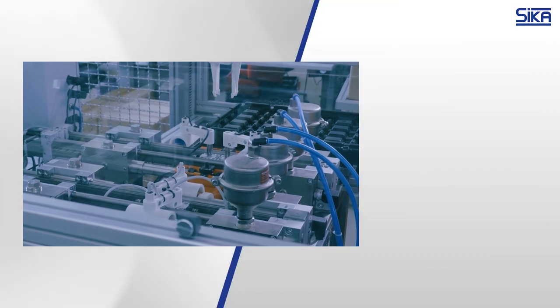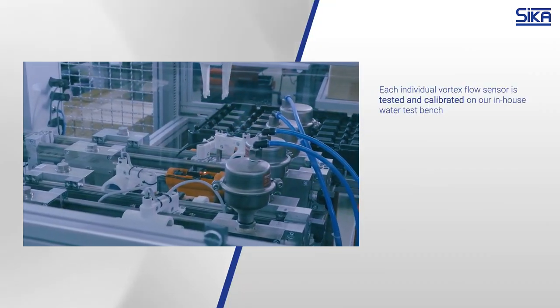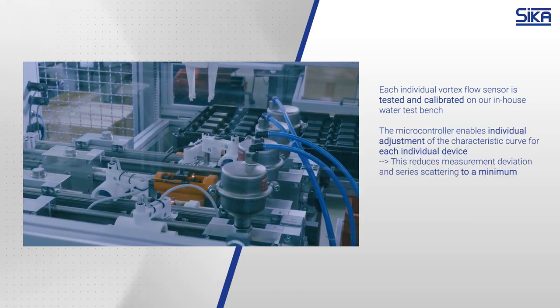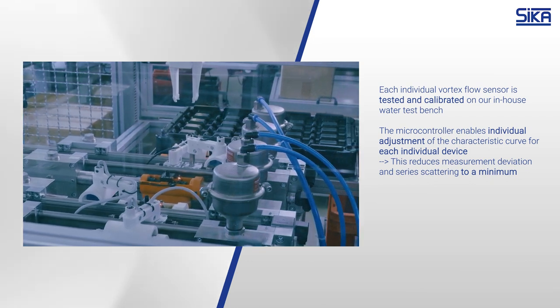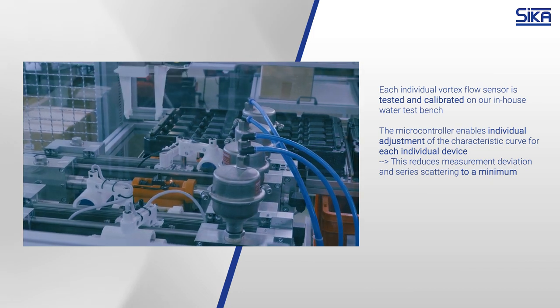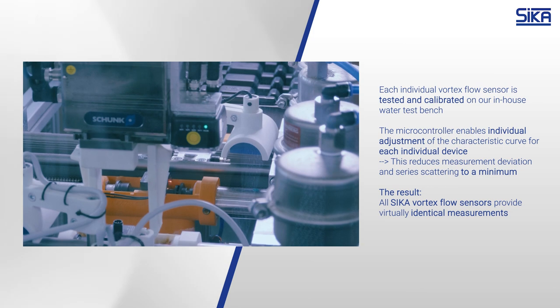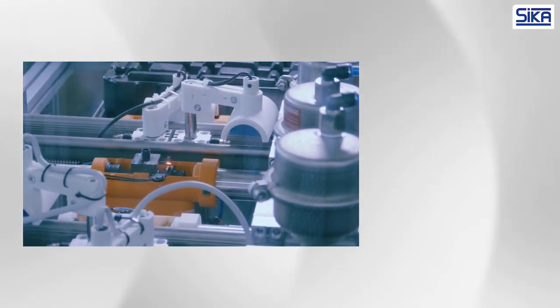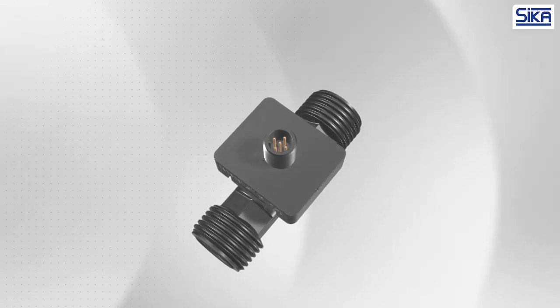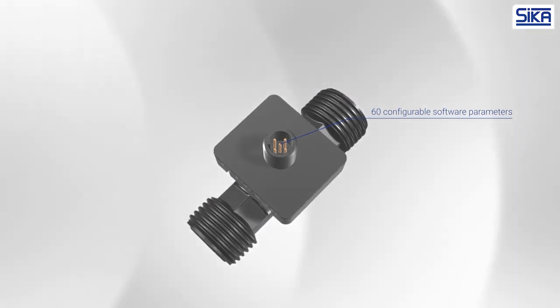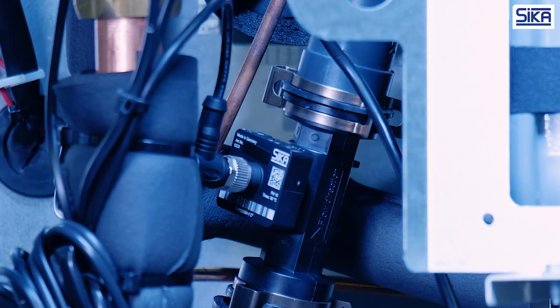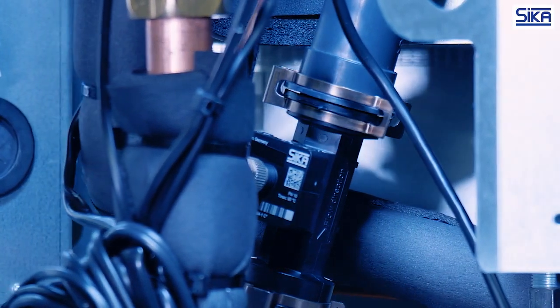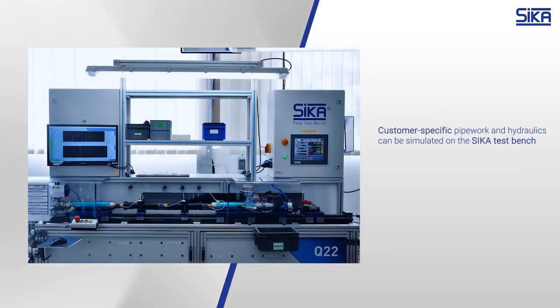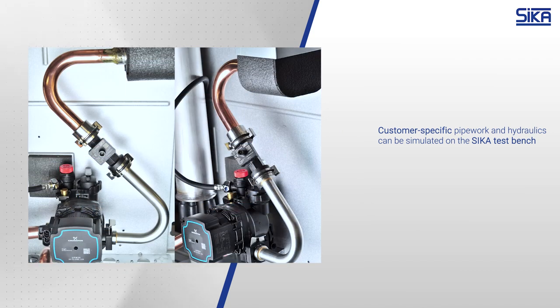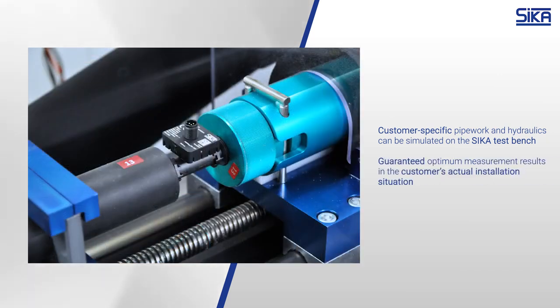And speaking of measurement quality, during production, every SIKA Vortex flow sensor is subjected to a quality assurance process in which the sensor is compared and calibrated at several test points on a water test bench. The built-in microcontroller allows us to adapt the characteristics curve individually for each device and to thereby reduce the measurement deviation and series scattering to a minimum. For the customer, this means that all SIKA Vortex sensors provide virtually identical measurement results. The microcontroller has an additional advantage though. On the VVX type, it is possible to set approximately 60 software parameters, thereby adapting the measurement to customer-specific installation situations. This takes place at the SIKA test lab. Here, SIKA can integrate customer-specific pipework or entire hydraulic systems into the test bench and thereby optimize the measuring performance for the actual installation situation.